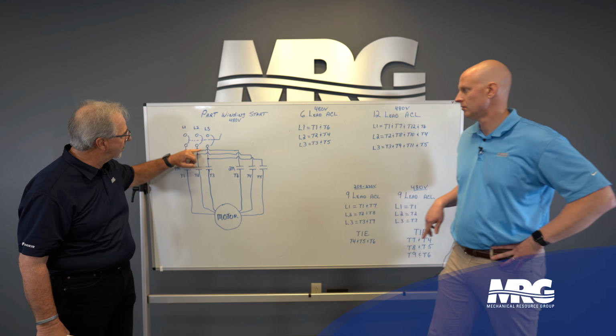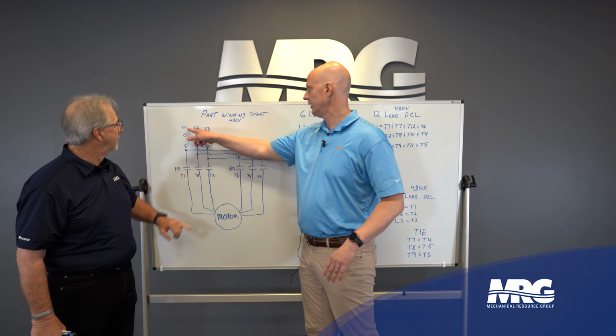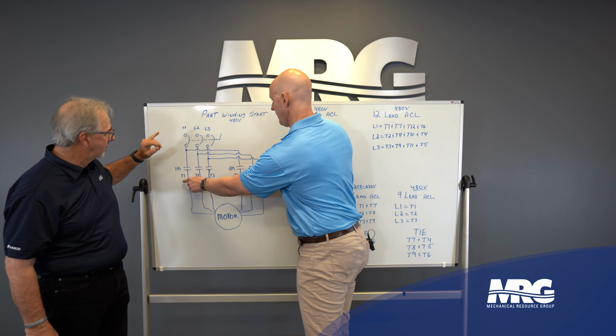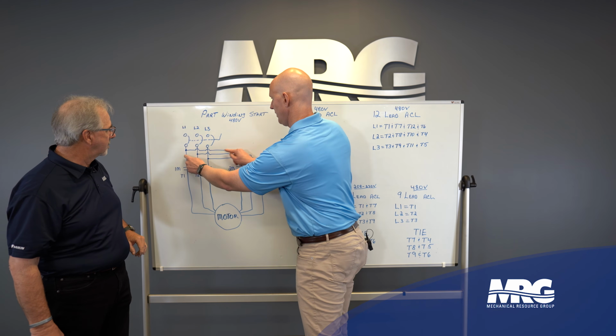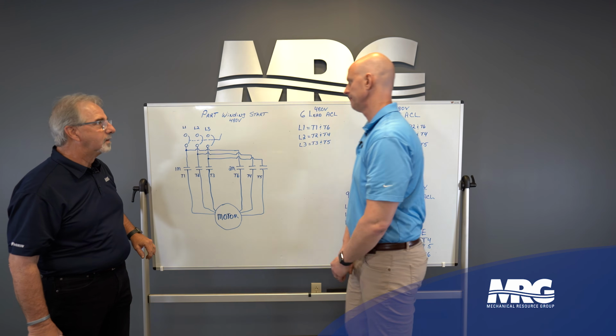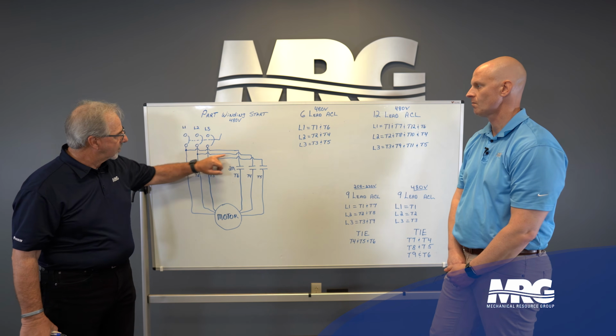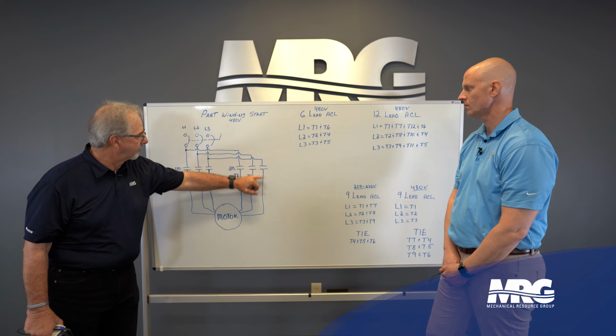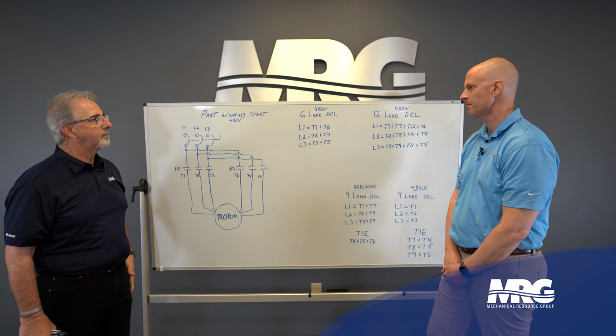So if you notice, phase A comes in. So we got 1 here, right? L1. And then we got 1 and 6. They're going to come up and hit 1 right there. And then 2 and 4 will connect, 3 and 5 will connect. Just like what we have for the across the line.